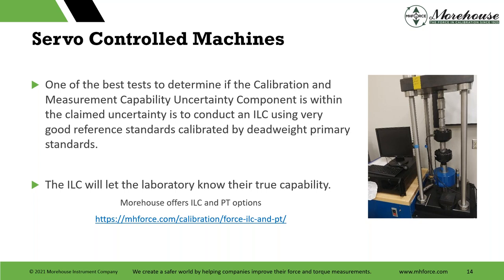Those numbers really determine if you have your CMC uncertainty parameters or your uncertainties right, and that will let you know your true capability. And that is just between us. We can send it out where we never see your results. You fill in the sheets. You can self-certify them. It is a big help if you want to know those extra error sources and if you want to fine-tune your machine. Oftentimes, I'll recommend somebody do that before they participate in a formal PT because that helps you gain confidence. You really don't want to get to the point where you fail your PT. It's a lot easier to know that answer, right?